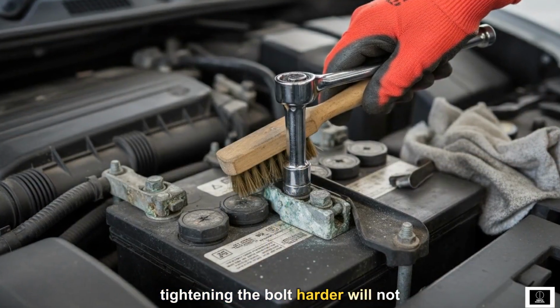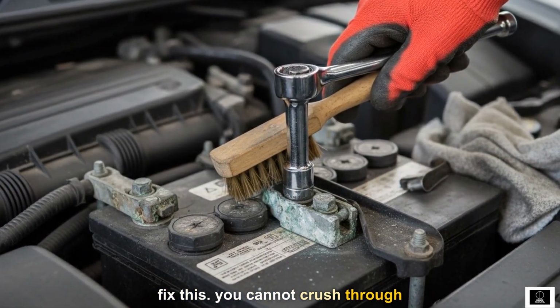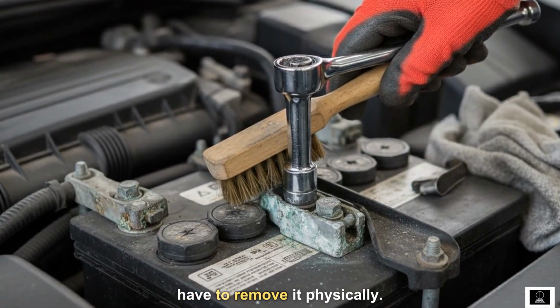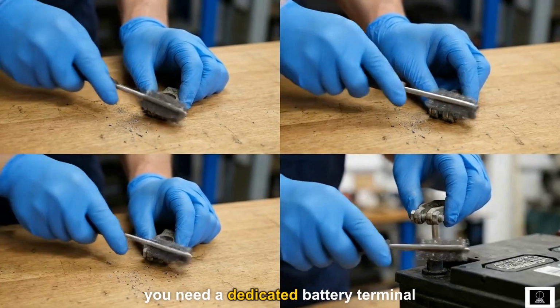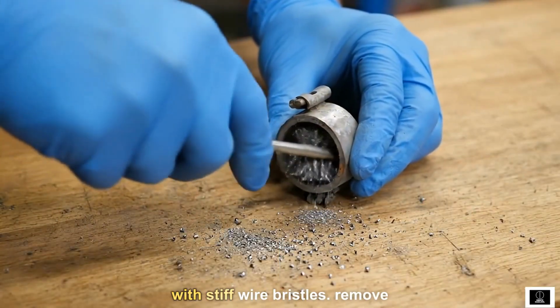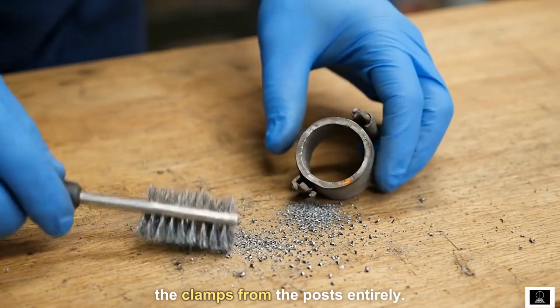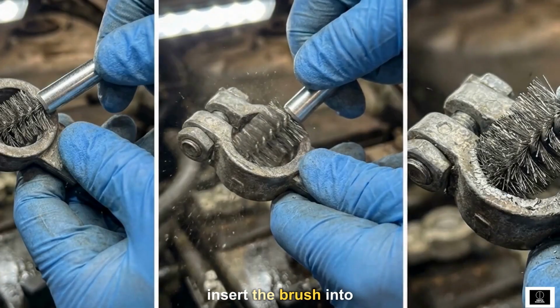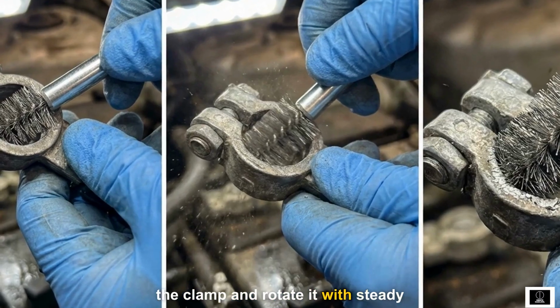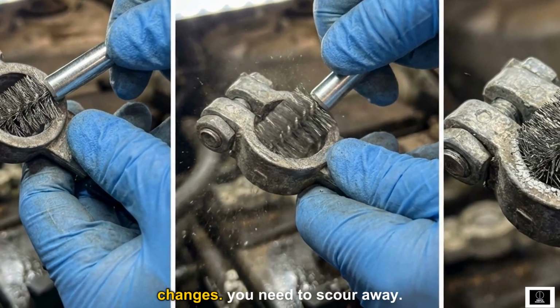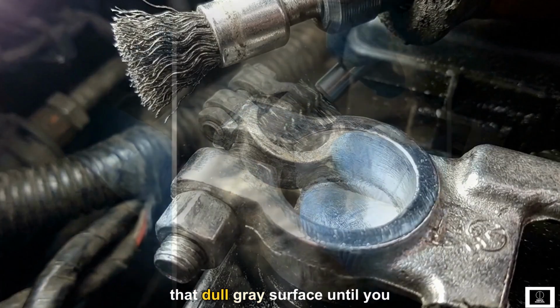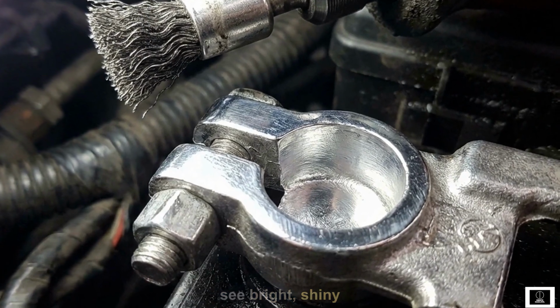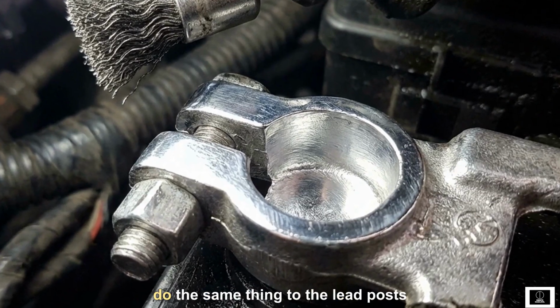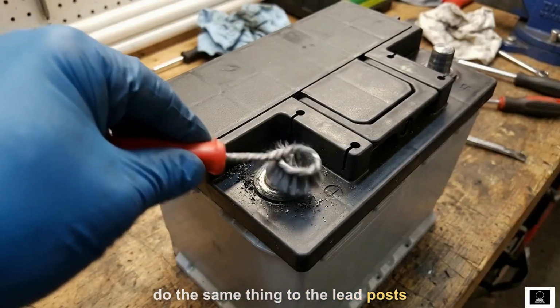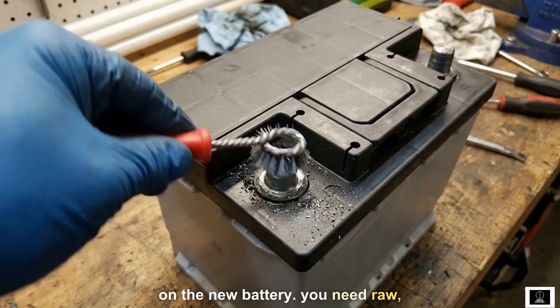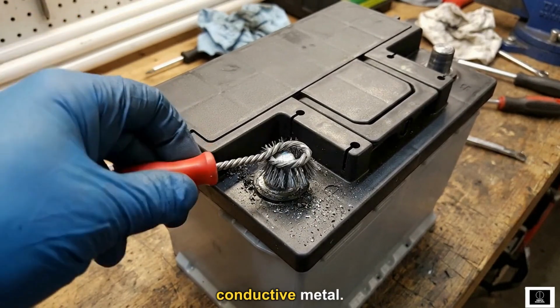Tightening the bolt harder will not fix this. You cannot crush through that chemical film. You have to remove it physically. You need a dedicated battery terminal cleaning tool with stiff wire bristles. Remove the clamps from the posts entirely. Insert the brush into the clamp and rotate it with steady pressure until the metal changes. You need to scour away that dull gray surface until you see bright, shiny silver. It should look like chrome. Do the same thing to the lead posts on the new battery. You need raw, conductive metal, touching raw, conductive metal.